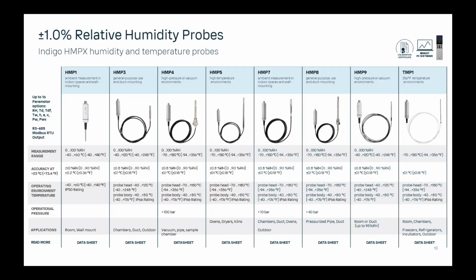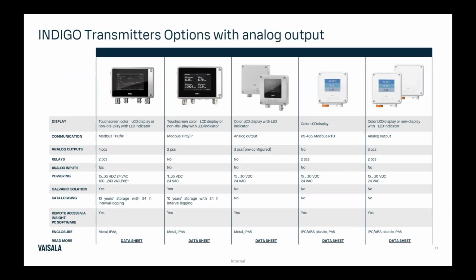So these all come with traceable calibration certificates to ISO 9001 compliance. That's done at the factory as standard and will come with a certificate when it's delivered to you. These on their own can operate with a Modbus RTU protocol in terms of data transmission, which can be used with the M12 connection on each of these probe bodies. However, if you were looking to have, say, an analog output, or you wanted to see a display readout in real time, you could pair these with our line of Indigo transmitters. So these are all of our permanently installed transmitters.